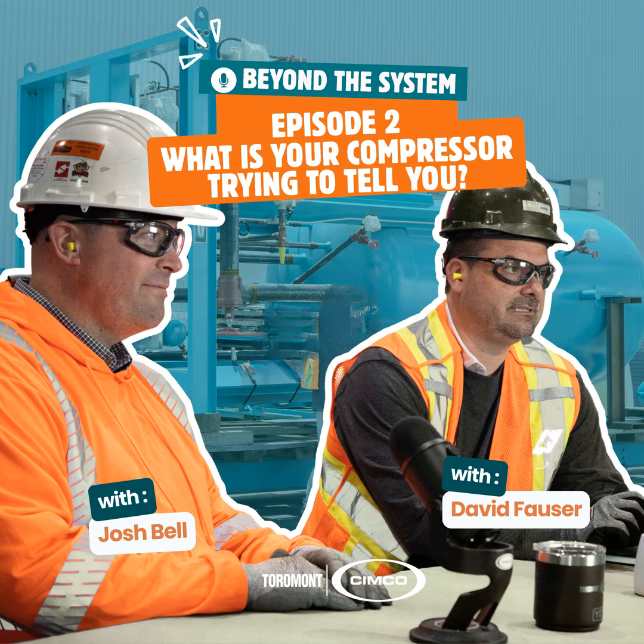So when you're changing out your compressor at 20 to 25 years, maybe 30 years on a well-maintained machine, you should look at how far back you go in the system. Is there better insulation? Are there different piping practices we use now? Could it be moved to a safer location or a more accessible location? A lot of factors come into play.